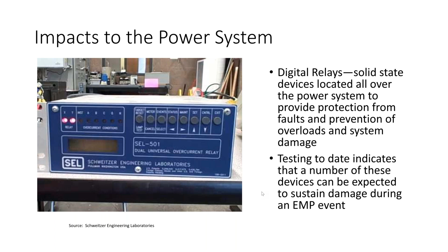And I'm brutally oversimplifying this because there are so many factors involved with how that energy, I mentioned the radiative energy being transferred into the control room of the substation. The factors involved with conducting the energy, that is the orientations of the cable, the shielding on the cable, the grounding of the cable, all that kind of stuff enters into this. But certainly the conductive energy issue is a potential problem, and will have to be dealt with on the electric system to be able to protect these digital relays from damage in an EMP event. John, if we go to the next slide, please.